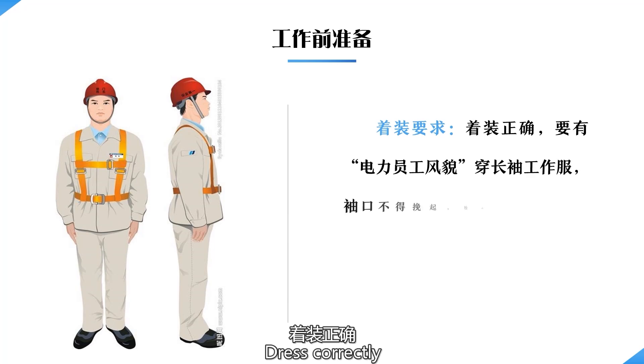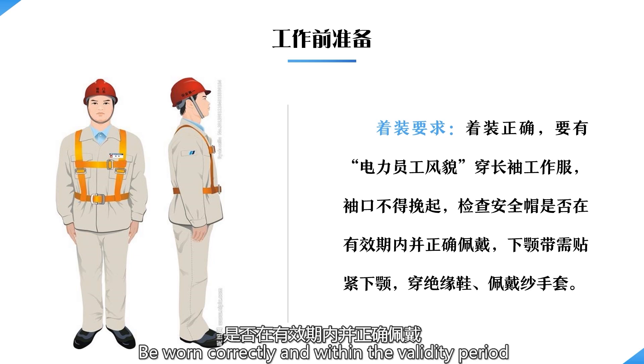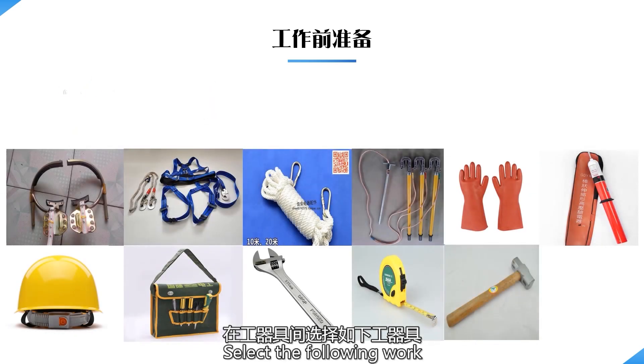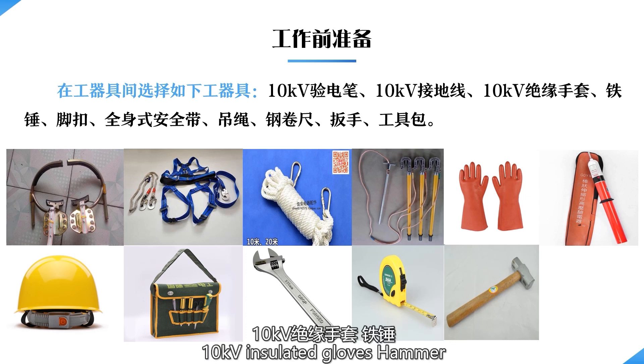Pre-work preparation: dress correctly to look like a power employee. Wear long-sleeved work clothes; cuffs should not be pulled up. Check that the helmet is worn correctly and within the validity period; jaw straps should be tightly fitted to the jaw. Wear insulated shoes and gauze gloves. Select the following work equipment from the equipment room: 10 kilovolts tester, 10 kilovolts ground wire, 10 kilovolts insulated gloves, hammer, foot buckle, full body safety belt.